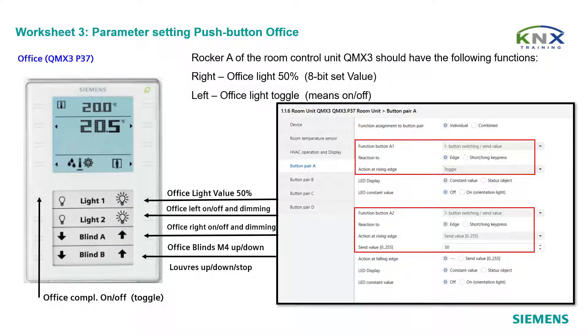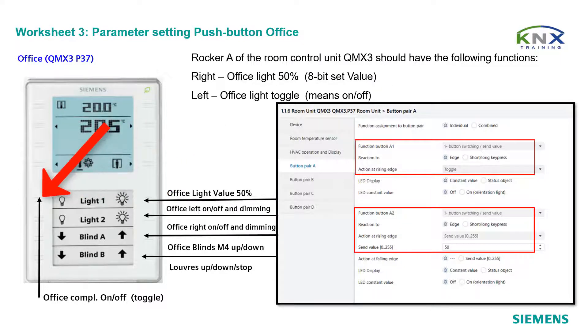Parameter setting push button office. Rocker A of the room control unit QMX3 should have the following functions: right button — office light 50% 8-bit set value; left button — office light toggle, meaning on/off with one button. A change is also planned for the office lighting. So far, the group control for both lights only turns on and off. But it is also possible to change the configuration so that you can use an in-between state, which is a light level of 50%.